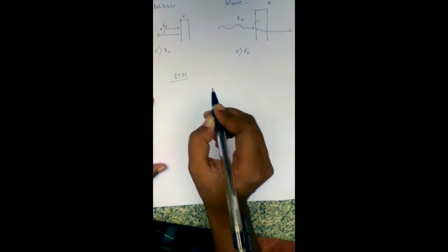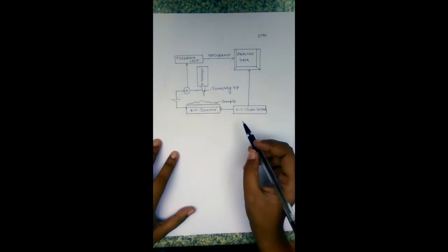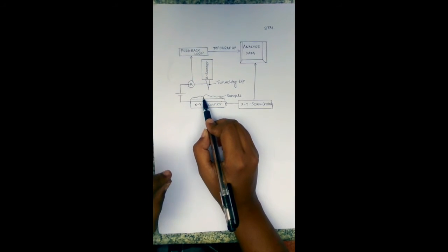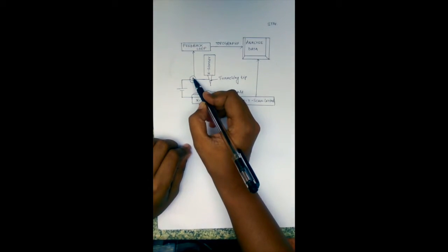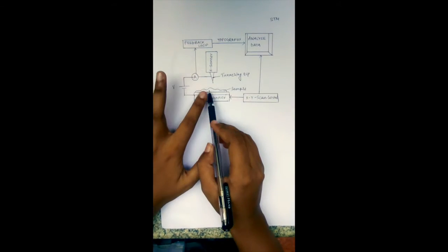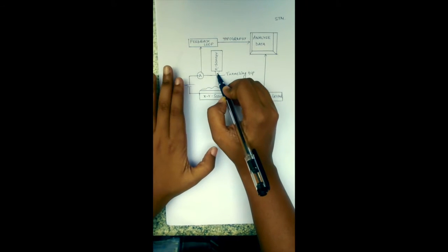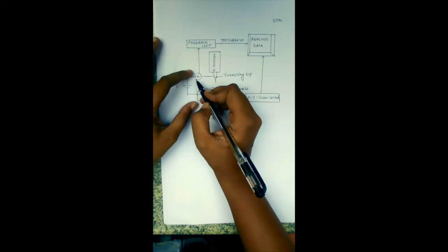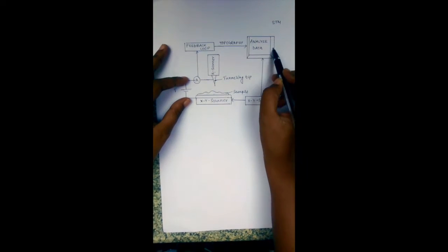This is the tunneling effect, and we are going to focus on the tunneling effect in the STM. The scanning tunneling microscope consists of a tunneling tip and the sample. The sample must have a conducting surface through which the electron can tunnel. A potential difference V is applied across the tunneling tip and the sample, so that the tunneling tip can be brought close to the sample and electrons can tunnel through. This creates a current which is detected through the feedback loop and topography to analyze the final data.